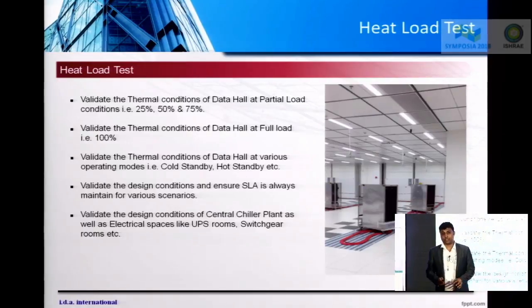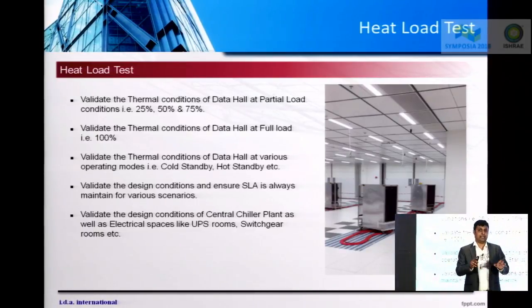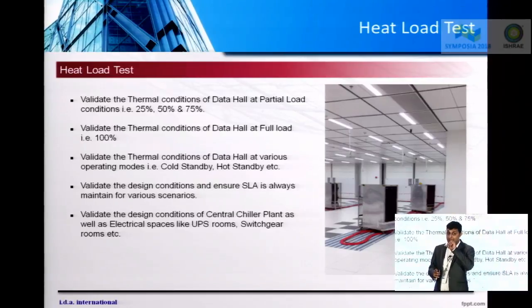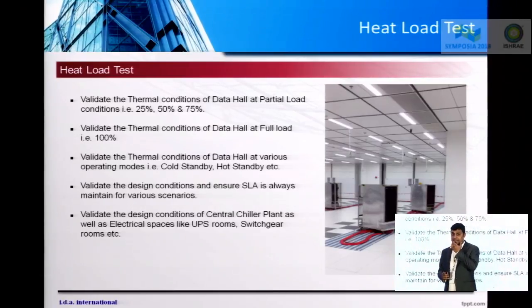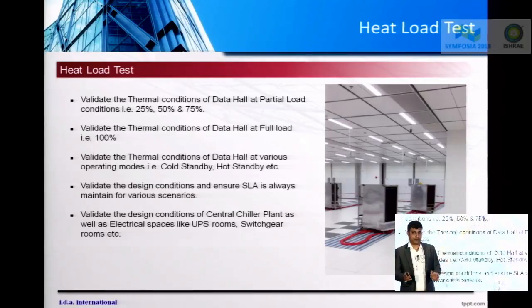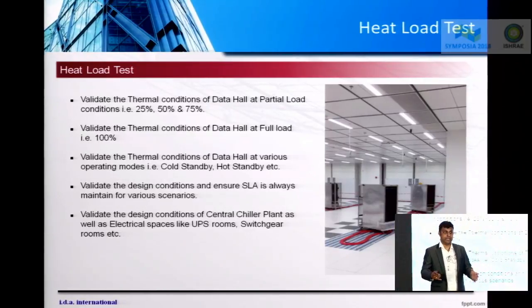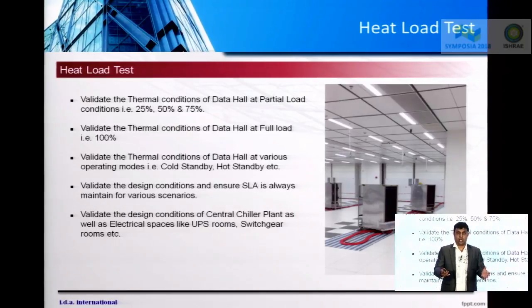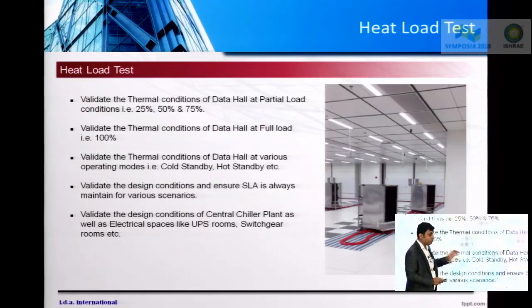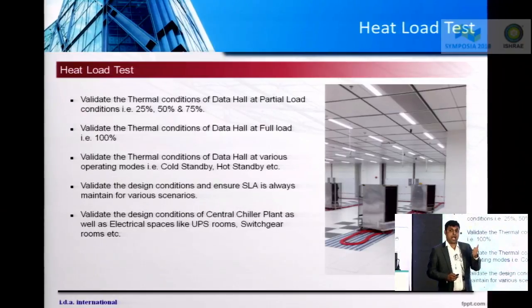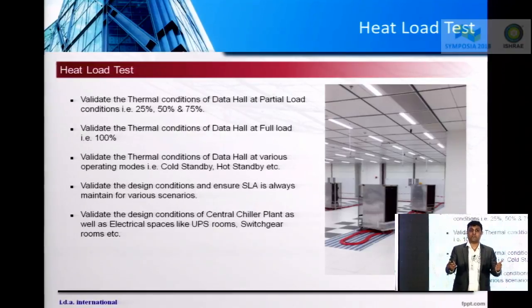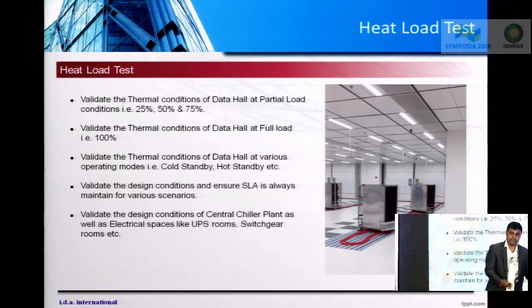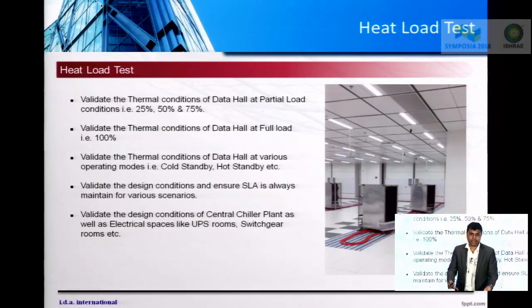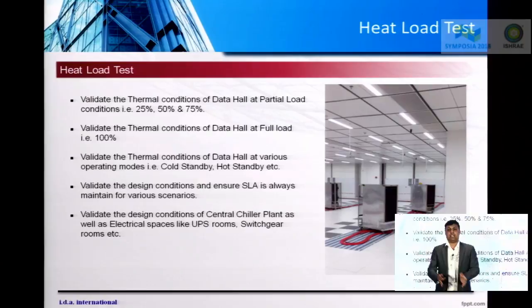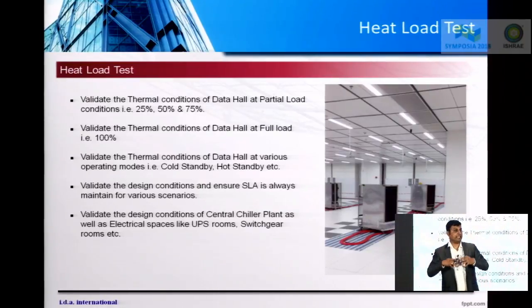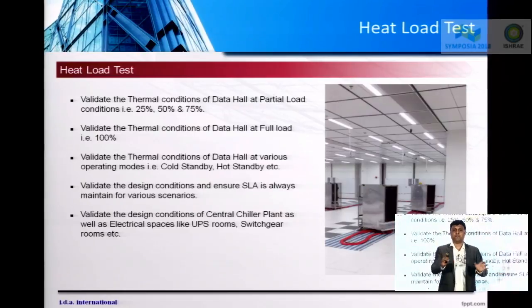Now let's jump to the heat load test. Now heat load test, as I said, the integrated system test is divided into two parts. The first is a heat load test, and second is an integrated system test. A heat load test is very important because you're trying to create or simulate an actual scenario in the data hall. So the purpose of heat load test is I have to verify the thermal condition of the data hall in cold aisles, in hot aisles, at the return side of the CRAC, at the supply side of the CRAC, during partial load condition as well as during full load conditions. So basically I'm verifying the temperature profile of the data hall at partial and full load condition.